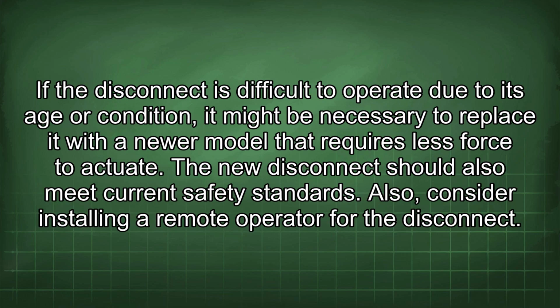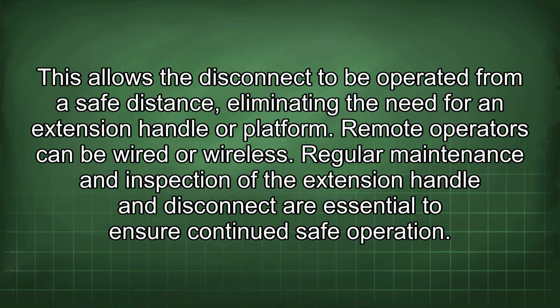If the disconnect is difficult to operate due to its age or condition, it might be necessary to replace it with a newer model that requires less force to actuate. The new disconnect should also meet current safety standards. Also, consider installing a remote operator for the disconnect. This allows the disconnect to be operated from a safe distance, eliminating the need for an extension handle or platform. Remote operators can be wired or wireless.